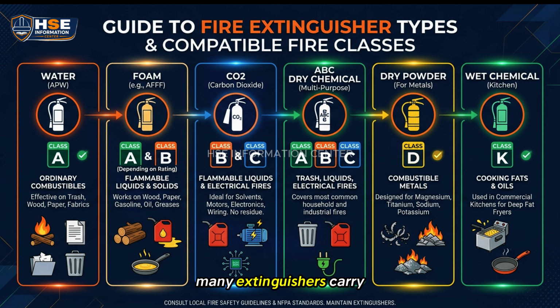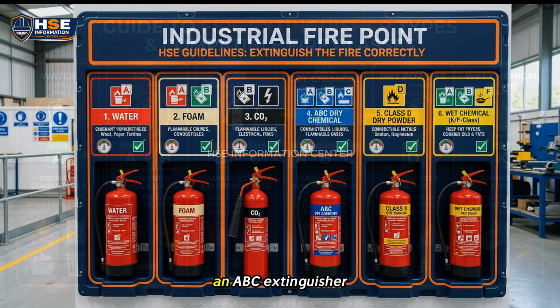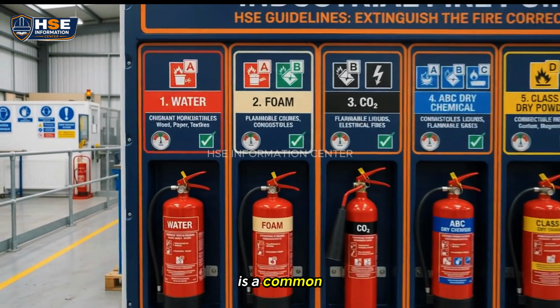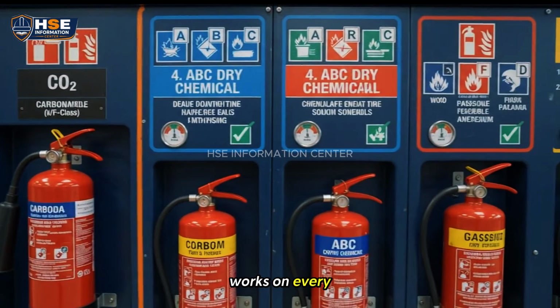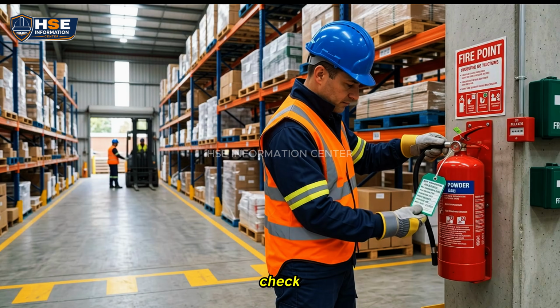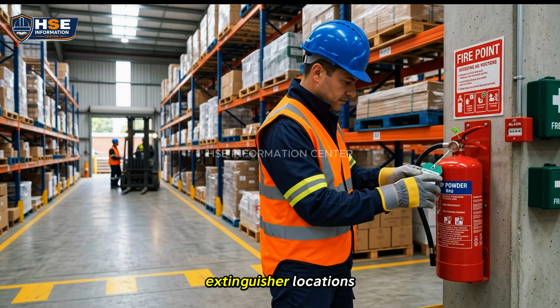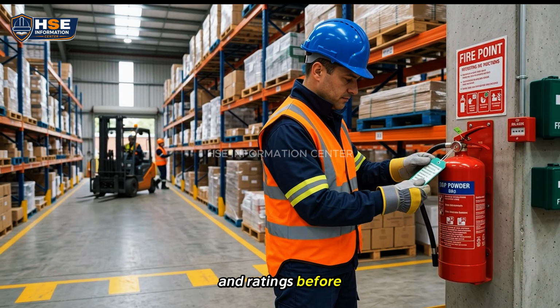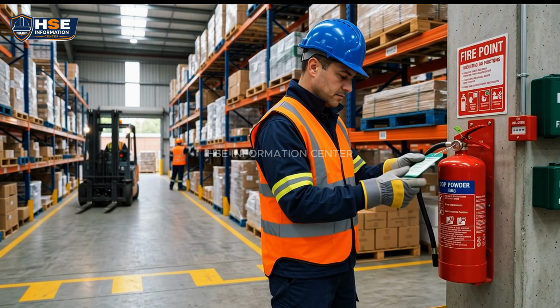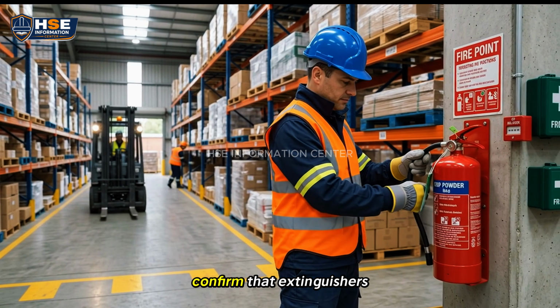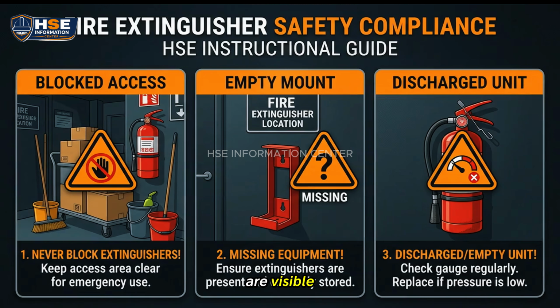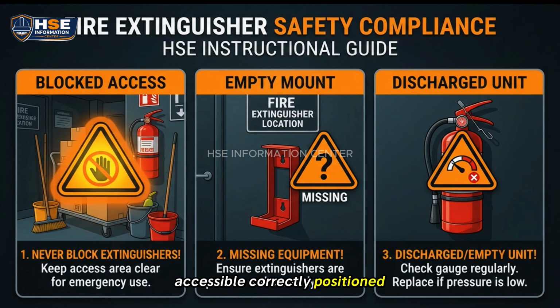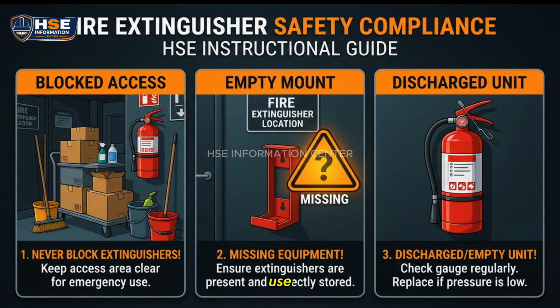Many extinguishers carry more than one rating. An ABC extinguisher is a common example. This does not mean every extinguisher works on every fire. The extinguisher label remains the final check. Workers should learn extinguisher locations and ratings before an emergency occurs. During normal inspections, confirm that extinguishers are visible, accessible, correctly positioned, and ready for use.